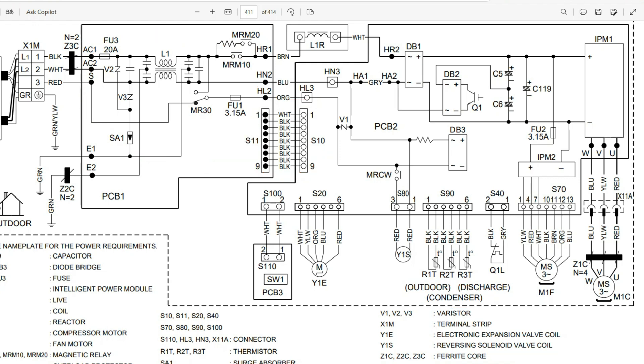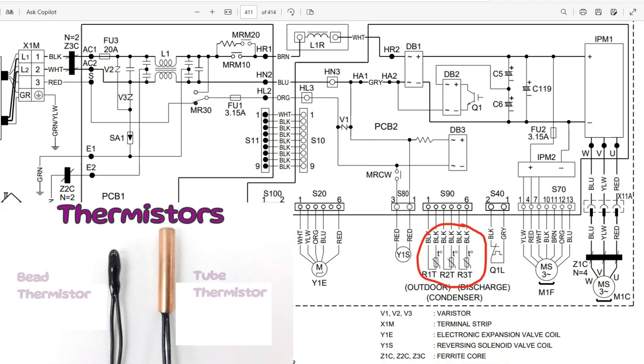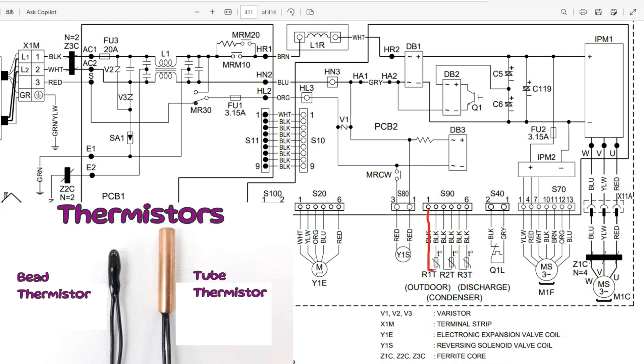There are different types of sensors in these systems. Some are going to be digital — anything reading frequencies or voltages will be digital sensors. But we also have sensors called thermistors. Basically, a thermistor is a resistor whose resistance value changes with changes in temperature or pressure. The PCB would send out 5 volts DC, the thermistor will have a different resistance value based on the temperature, and it'll filter that voltage and send it back to the PCB. We can actually assign a certain temperature to a certain voltage.